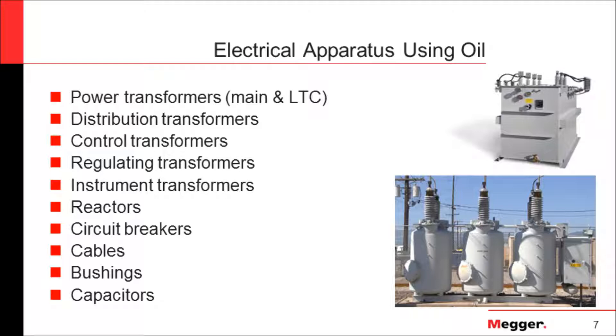When we talk about oil, we use it in various different electrical apparatus. When you go to a substation, there are high voltage equipment operating at various different loading conditions. During online operation, they need some sort of insulating medium to either separate the windings or to separate the load side from the source side. In those kinds of electrical apparatus, we use insulating oil, and you will find it in power transformers, circuit breakers, bushings, CTs, and so on.